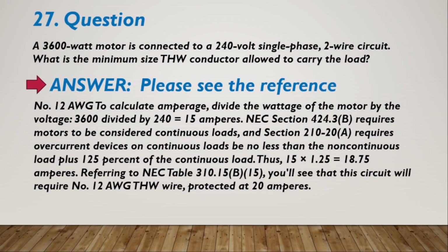Question number 27. A 3600 watt motor is connected to a 240 volt single phase 2-wire circuit. What is the minimum size THW conductor allowed to carry the load? Please see the reference.